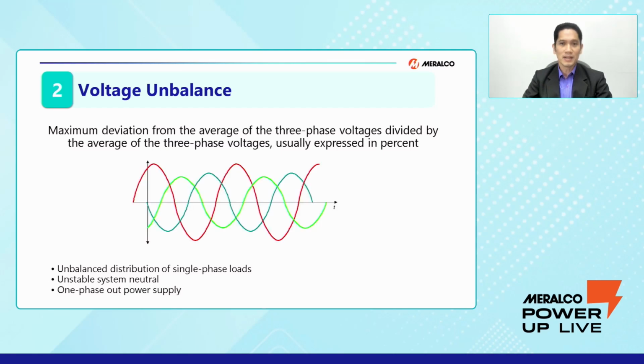So for the voltage unbalance, as defined in the Philippine Distribution Code, this is the maximum deviation from the average of the three-phase line voltages divided by the average of three-phase voltages, usually expressed in percent. It might be due to the unbalanced distribution of single-phase loads, unstable system neutral, or one phase out power supply. When we say one phase out, for a three-phase system, one of the phase voltages or line voltages was zero or out. So that will result in voltage unbalance.